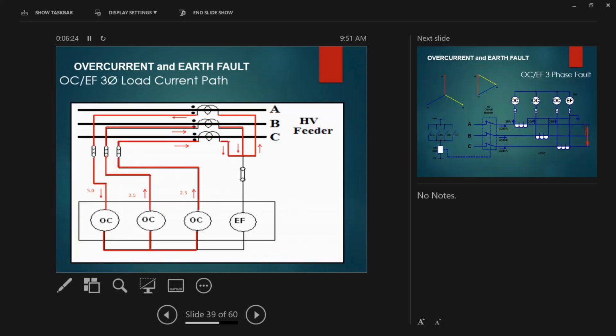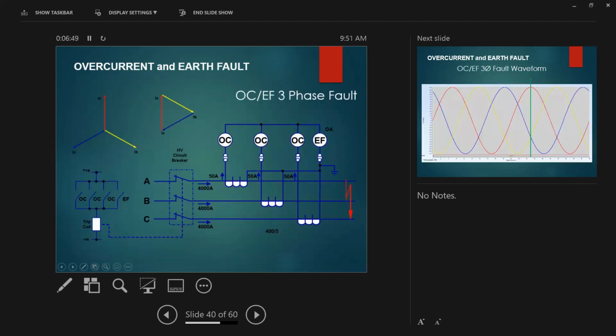So for this one, even though I have an unbalanced circuit, 5, half of that here, half of that here, since I have a balanced angle, there will be no flow of current here. So that one will loop to each other. This 2.5 will sum up and come up to 5 amps here. And so on. So that's how it goes. The angle is very important.